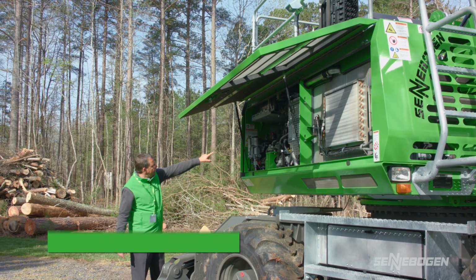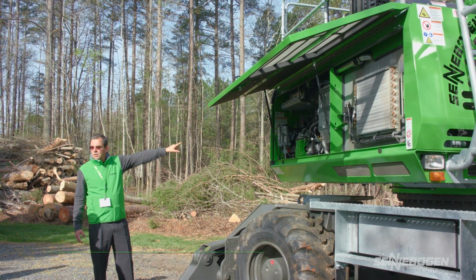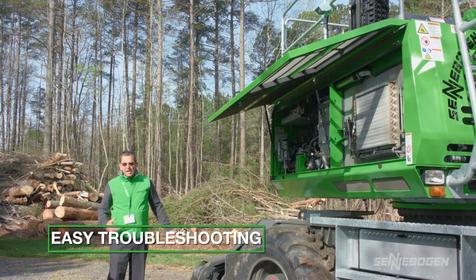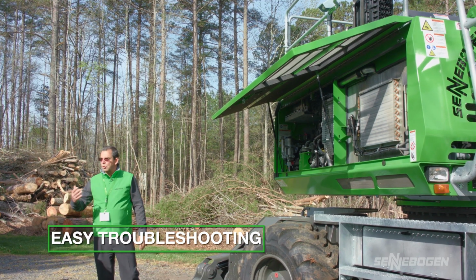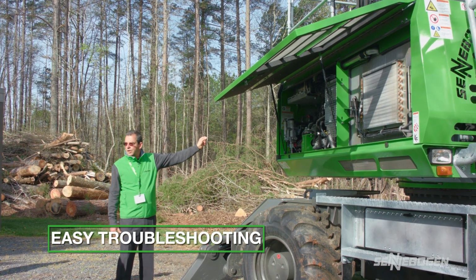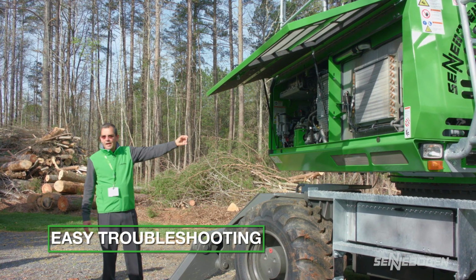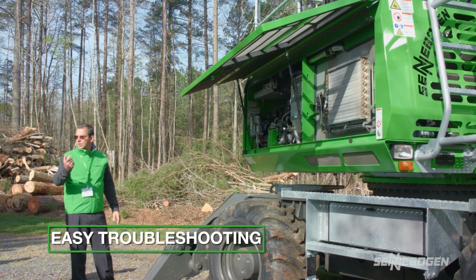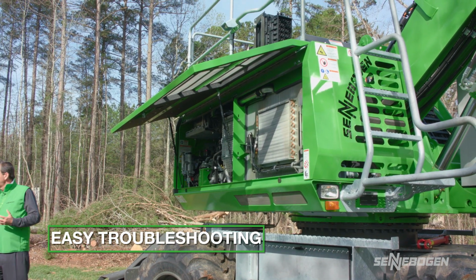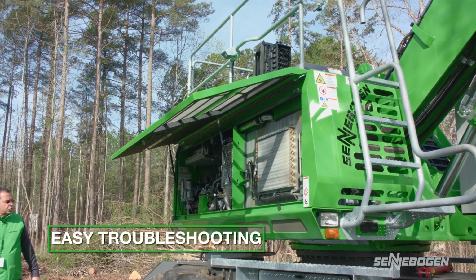As you can see over there, there are some red LEDs that are lit, right? What that means is that circuit is energized. So that simplifies drastically the troubleshooting of the equipment, because you know if that function is not working and that LED is on, the cables are okay, the switch is okay, power is getting there, so it's either the solenoid coil or it's the valve itself. So these are things we do to improve uptime and to reduce the troubleshooting time.